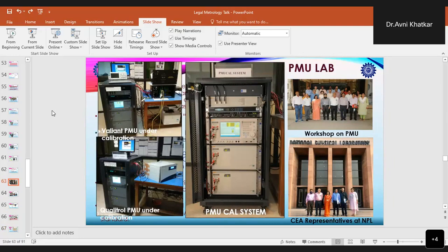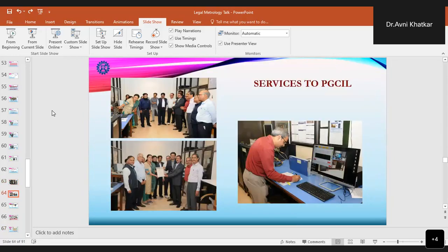So we have this PMU calibration system. We are providing services to different manufacturers for their PMU calibration. Also, different representatives generally come from CEA to see what this system is and how it can be used for the nation. And we are also providing calibration services to PGCIL. Recently, we have calibrated PGCIL's PMU calibrator system, which can be further used to calibrate all the PMUs. So that system is also now traceable to the national standards of the country.